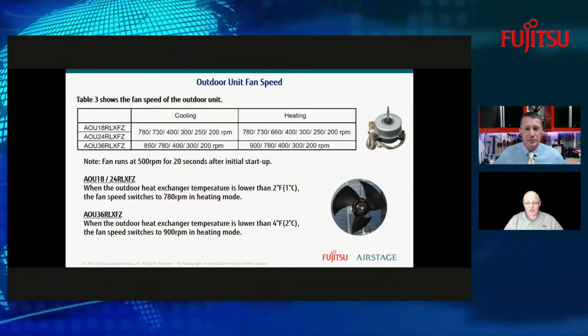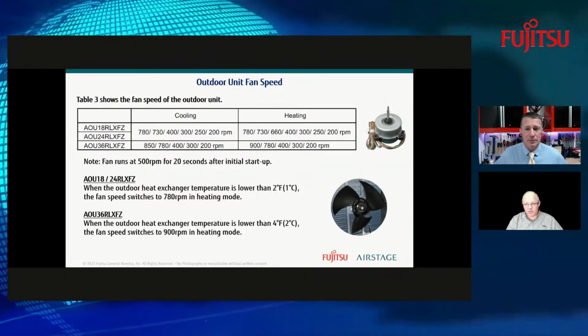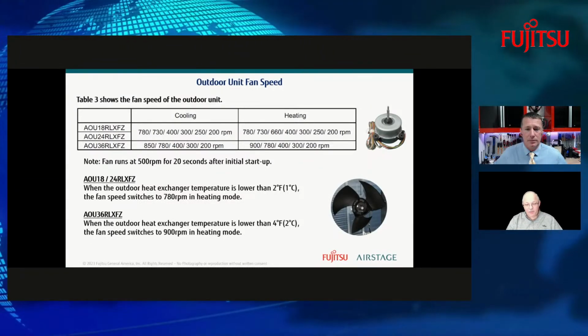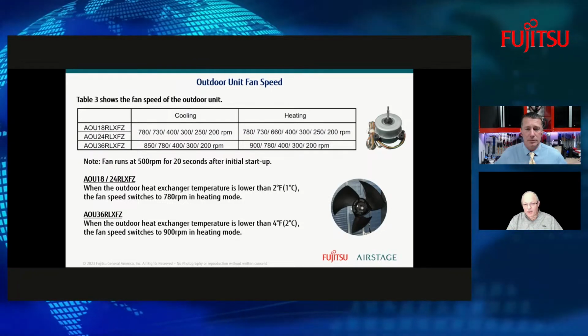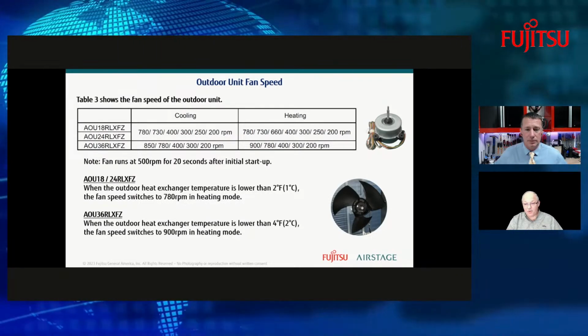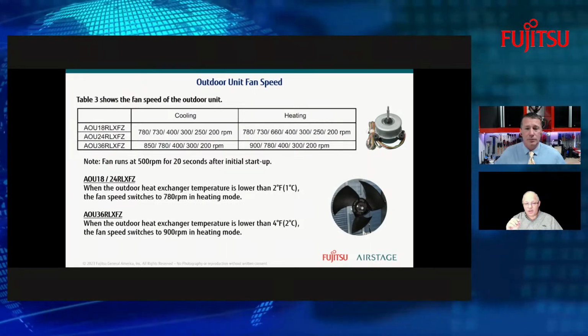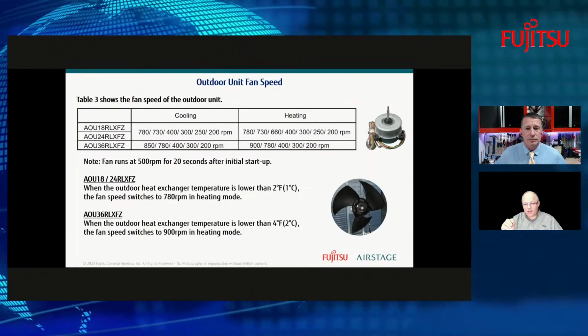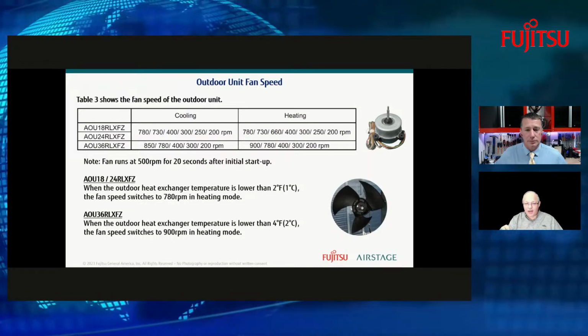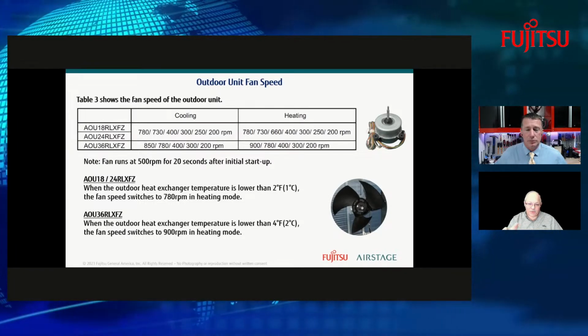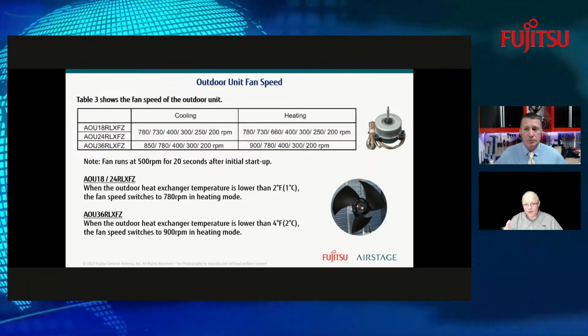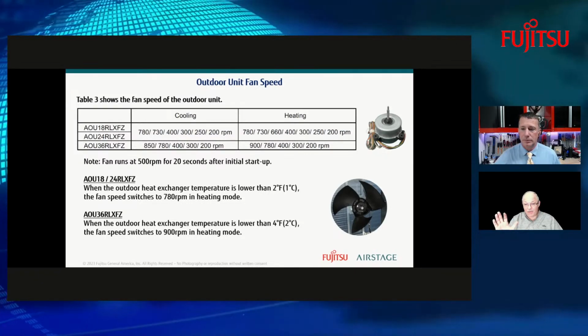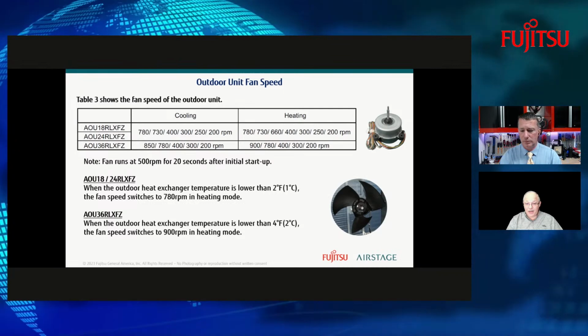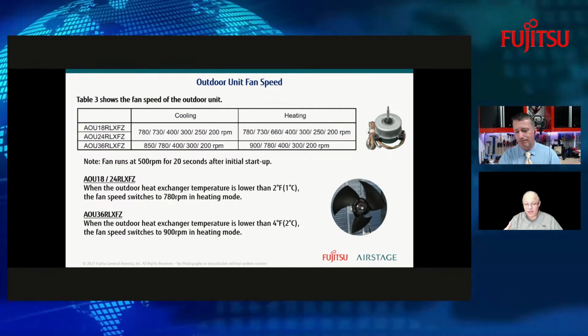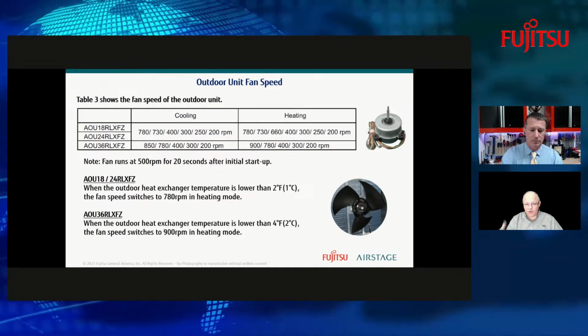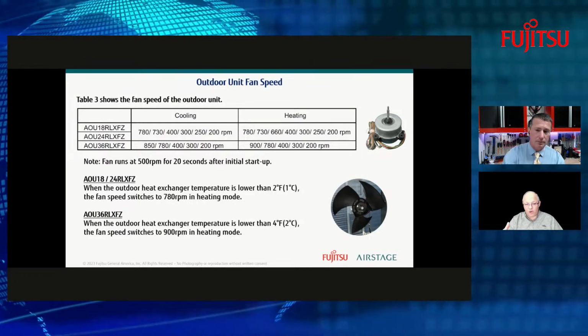That's correct. And so when we start looking at things, not just the compressor, but now the outdoor fan motor, depending on the model, again, will depend upon what RPM it's designed to run at. Right. And so what's happening is it's looking at the temperature of the heat exchanger. Now, there's a lot of things that could impact that. If it was a dirty heat exchanger, then the system would basically say, your subcooling's off. I need to speed up the fan to try to get more air across that heat exchanger.